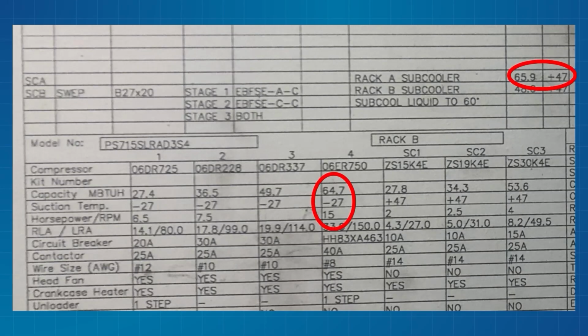So one thing to note about my rack subcooler. Let's look at A's. This is MBTUs, a little over 60,000, right? 5.5 tonnage. Around 5 3/4, just ballpark it, around 5.5 tons. So my subcooler is about 5.5 tons, and it's doing that at a 47-degree evaporator. Remember I said subcooling is similar to air conditioning pressures? This one's a little higher, but that's the idea. So I've got that going on.